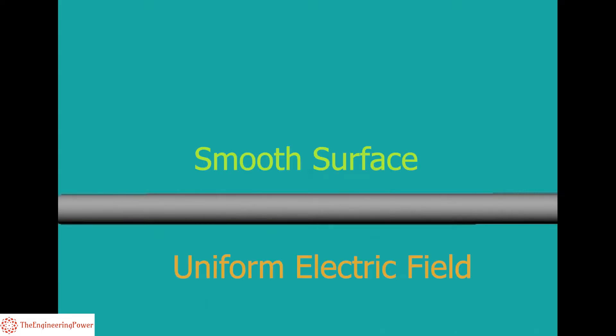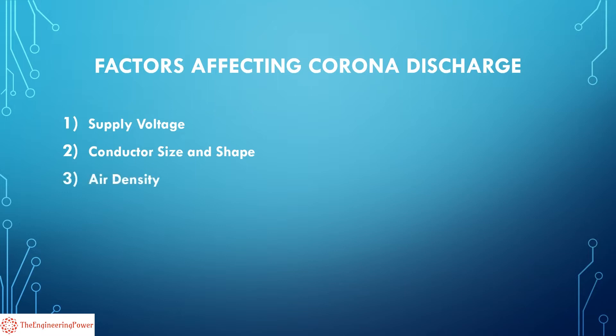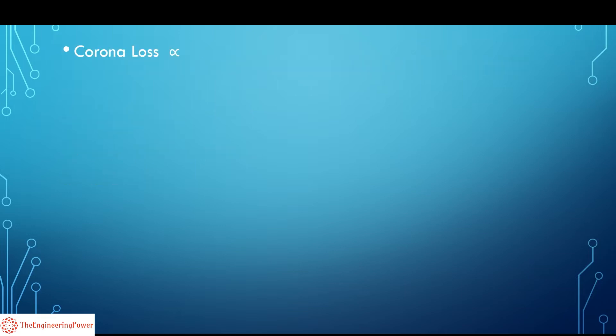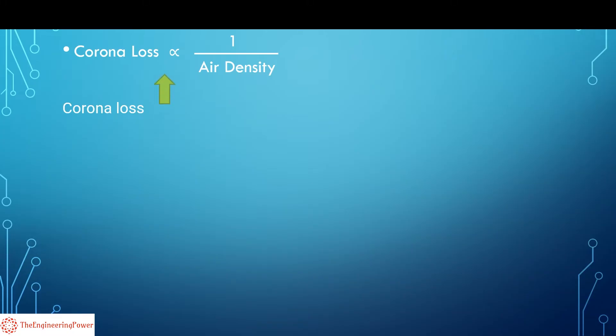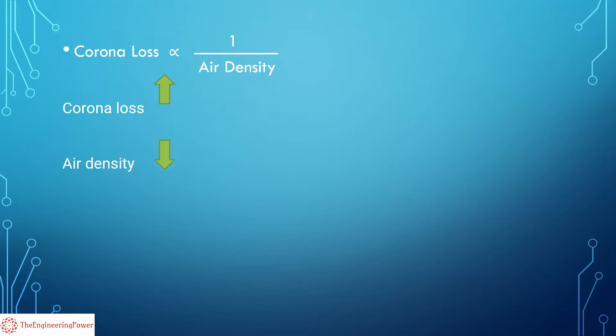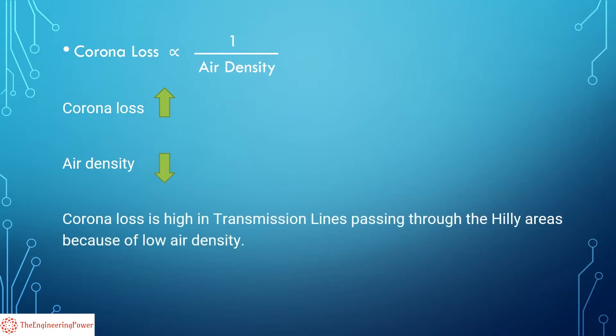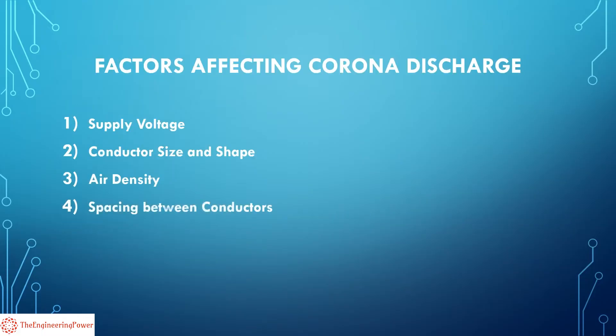Another factor is air density. Corona loss is inversely proportional to air density — that is, corona loss will increase with a decrease in air density, and vice versa. Corona loss is high in transmission lines passing through hilly areas because of the low density of air in those areas.